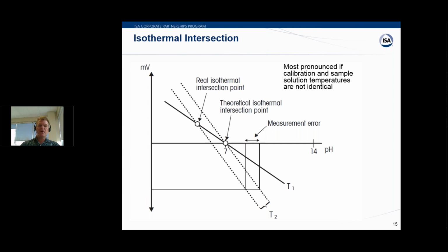Here is that Nernst equation at work. You can see that the slope changes as a function of temperature. Typically, we always try to condition our sample system for a pH system so that the temperature is constant. Now if you're putting your pH probe directly into the process, then of course you can do temperature compensation. If you have a temperature compensated pH electrode, effectively what you're doing is moving up and down the slope line, the slope that we see here, the solid black line.